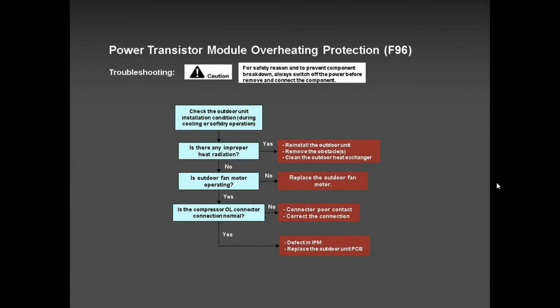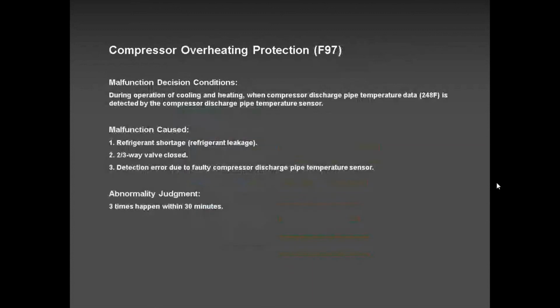Now again, if your job site is like a 2-3 hour drive, if I were you, I would take the outdoor board and the compressor. Start with the outdoor board. If I'm getting the same problem, then I change the compressor. But if it's a job site just an hour or half an hour drive, then I would just go with the outdoor PCB.